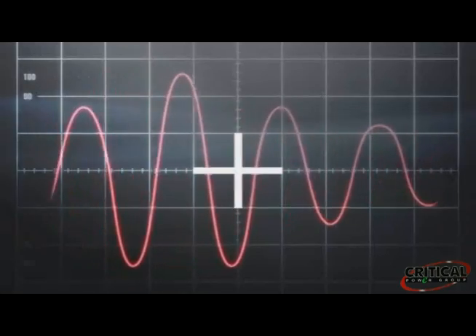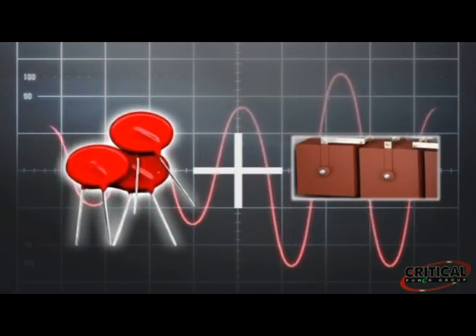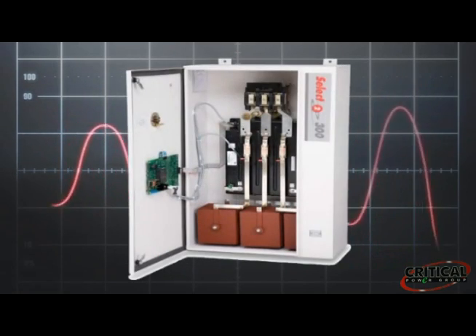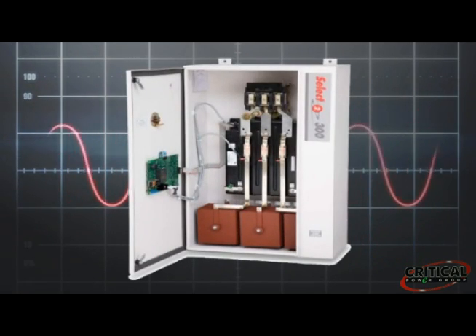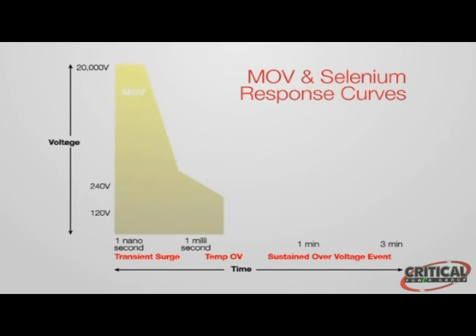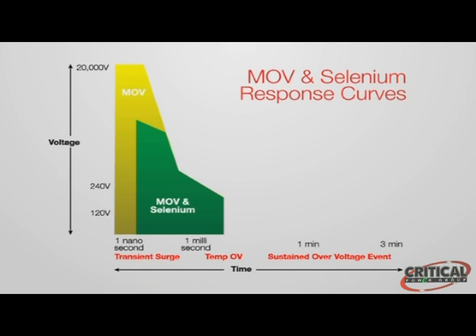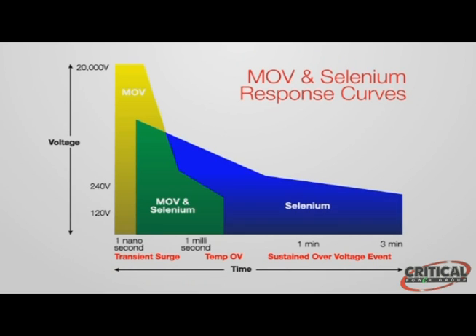CAPS uses a combination of MOVs with selenium cells to provide an effective strategy against transient surges and temporary overvoltage events. The MOVs handle high voltages of a very short duration. The selenium has a slightly slower response time, but can provide protection against lower overvoltage conditions that last longer. The MOV is the sprinter, the selenium is the marathon runner.